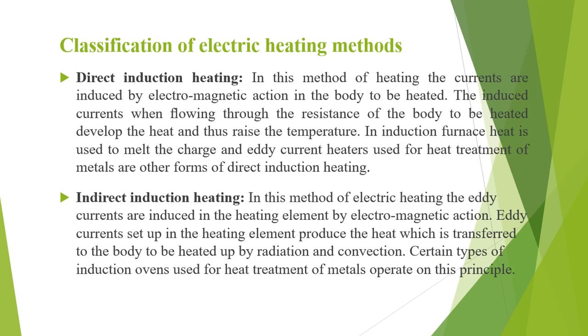Direct induction heating: in this method, currents are induced by electromagnetic action in the body to be heated. When these currents flow through the resistance of the body, it develops heat and raises the temperature. In induction furnaces, heat is used to melt the charge, and eddy current heaters are used for heat treatment of metals.